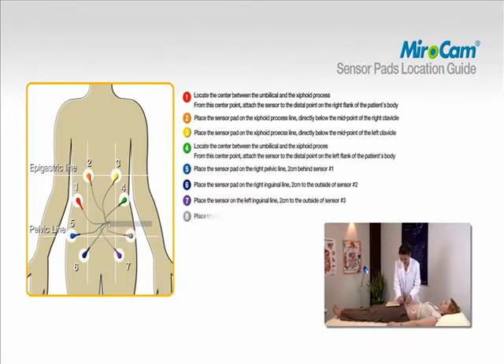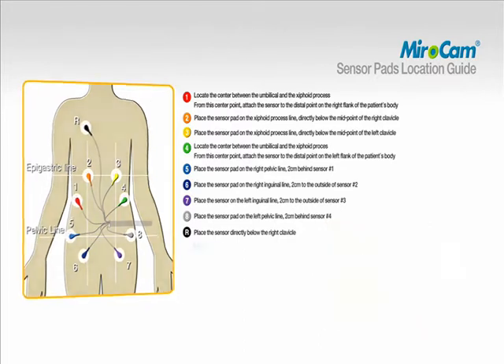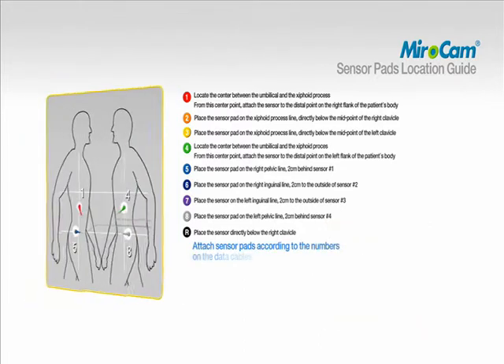To attach pad number eight, place the sensor pad on the left pelvic line, two centimeters behind sensor number four. To attach pad number nine, place the sensor directly below the right clavicle. The numbering of the data cables and sensor pad must match the specified area.